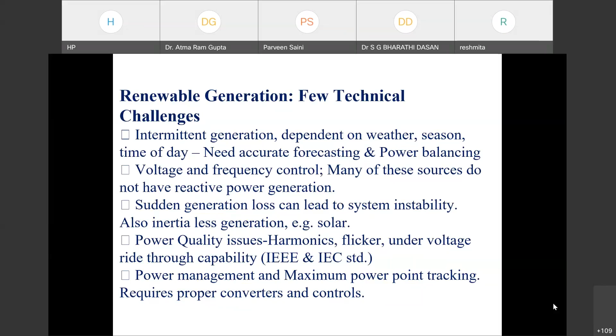Also inertia-less generation, that is in solar. So here sudden generation loss may occur, and due to this, the system may go into instability mode. Power quality issues are associated with the use of power electronics converters and devices. We have to address harmonics, voltage flickers, and under-voltage ride-through capability, and they have to be maintained as per IEEE and IEC standards. Power management and maximum power tracking is a little bit difficult with this technology, and it requires proper control and design of the converters and controllers used in this system.